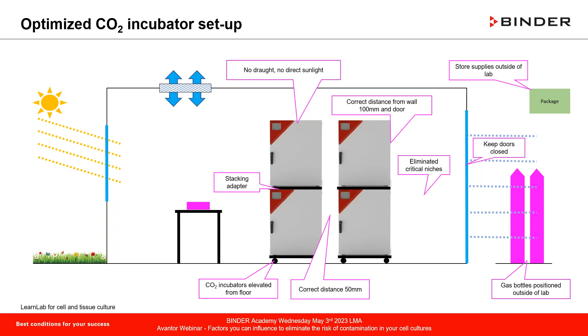With a stacking adapter, that is, ladies and gentlemen, not for the fixation, not that the upper one stands firm on the lower one. That is a thermal barrier, which then ensures that you can actually conduct a 180 degrees C hot air sterilization below while incubating on top at 37. Then we pulled away that water bath on a separate little table or corner or area. So there you've also reduced the risk by increasing the distance to the CO2 incubators.